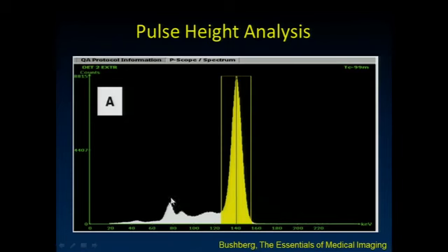Yeah, that's scatter within the collimator. That happens to correspond to the characteristic X-ray energies of lead, and our collimator is made of lead. So when events interact in the lead collimator and we get some characteristic X-ray production, we certainly don't want to include those in making our image.